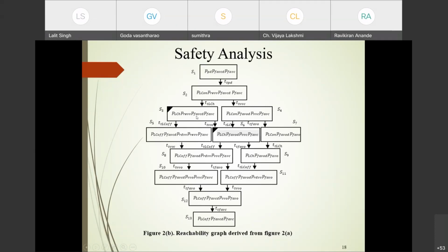And if you are able to see here, both the redundant and main sensor information represent that the fast acting valve is still in closed condition. So it is a very risky state, and I really need to avoid this state.